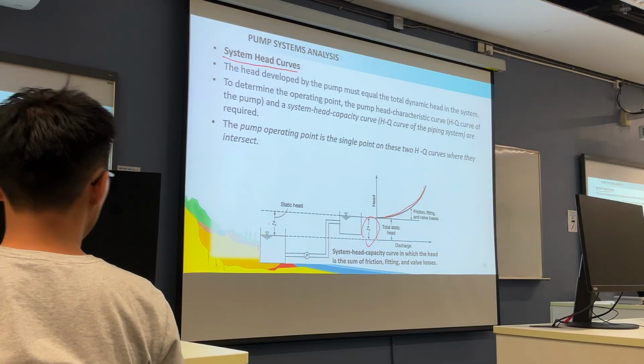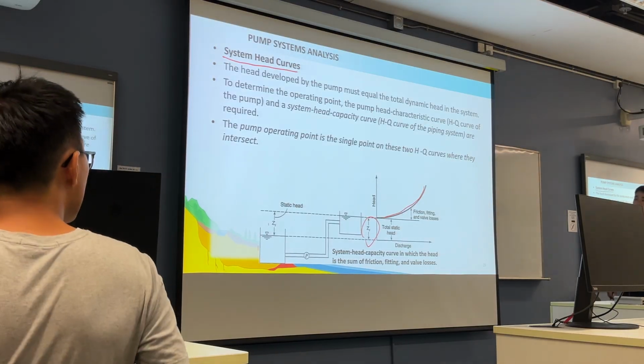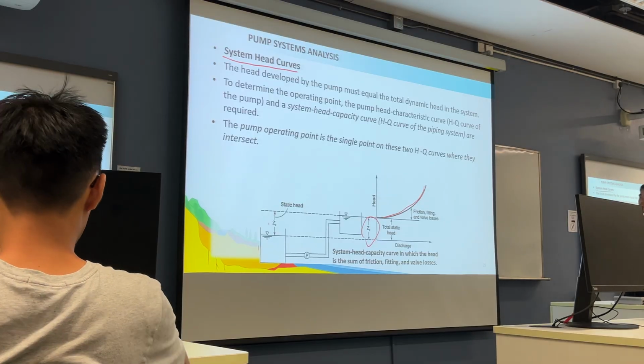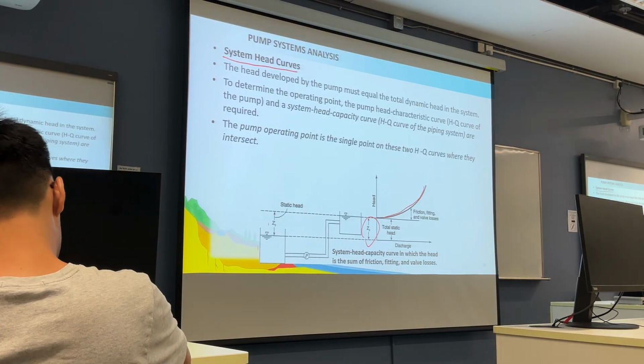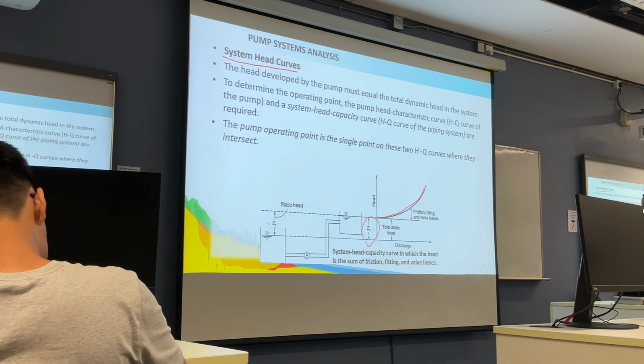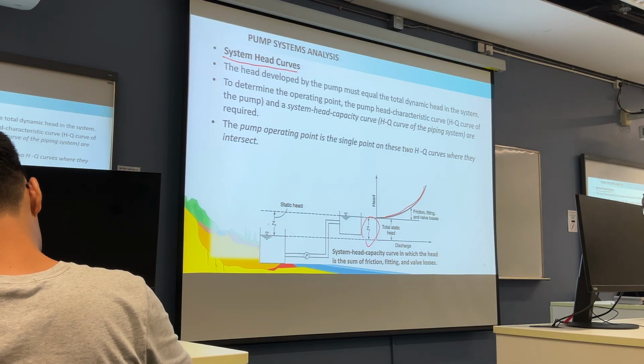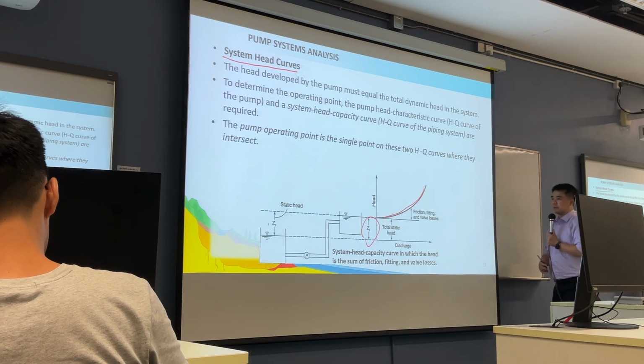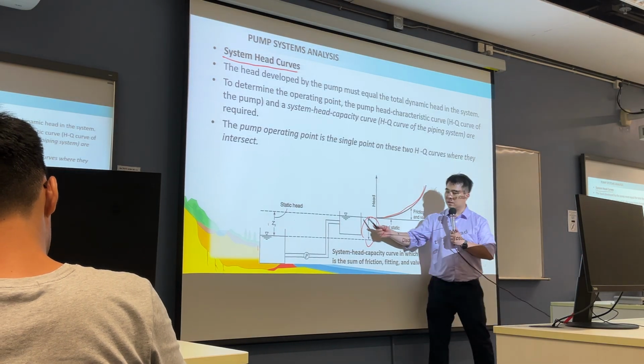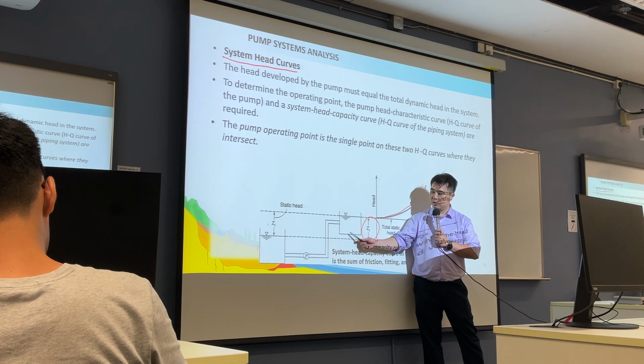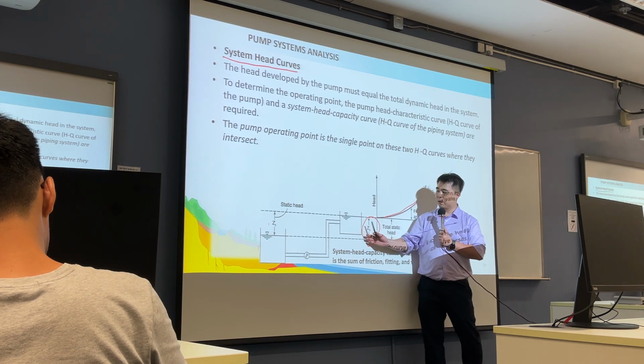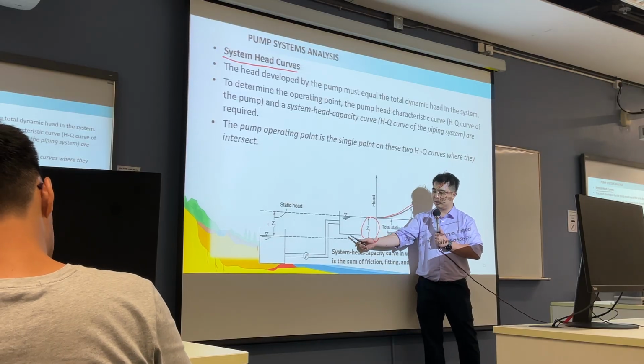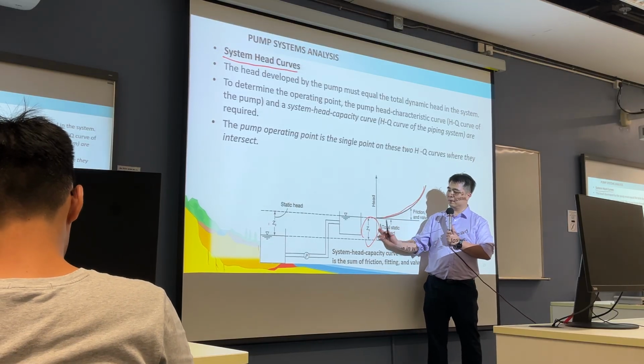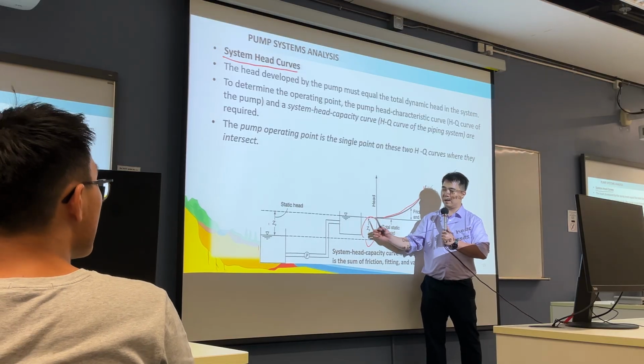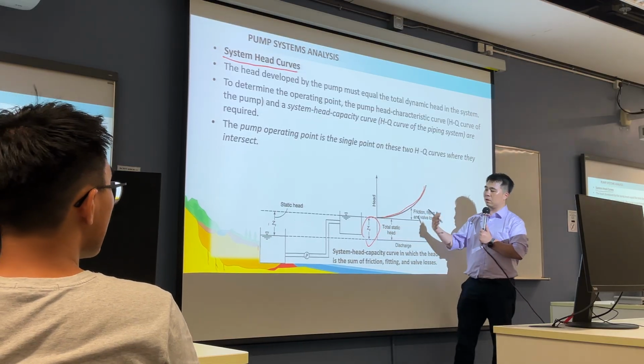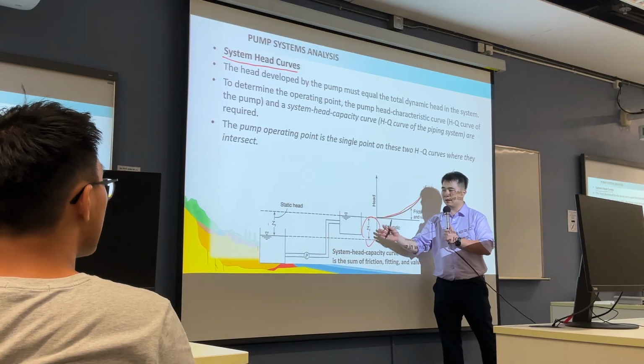So this one is called the static head for the pumping downstream. Static head uses the same head as the previous suction pump, okay. It seems a little bit confusing. Now, total static head means the elevation difference between the lower and upper reservoir, okay? Because the pump you apply to this system, at least, has to overcome this static head to make the flow happen. This is not considering the frictional loss and other things, okay?